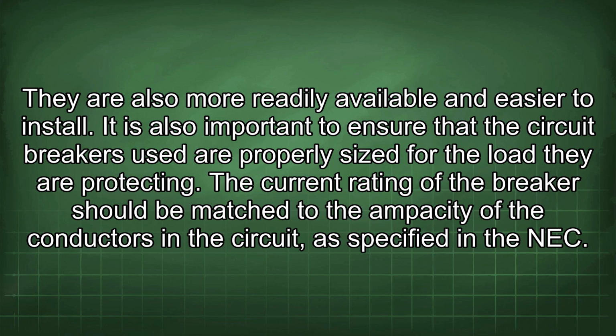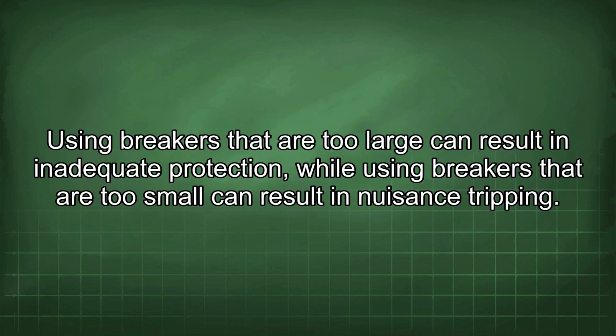It is also important to ensure that the circuit breakers used are properly sized for the load they are protecting. The current rating of the breaker should be matched to the ampacity of the conductors in the circuit, as specified in the NEC. Using breakers that are too large can result in inadequate protection, while using breakers that are too small can result in nuisance tripping.